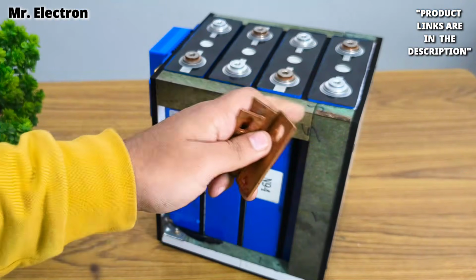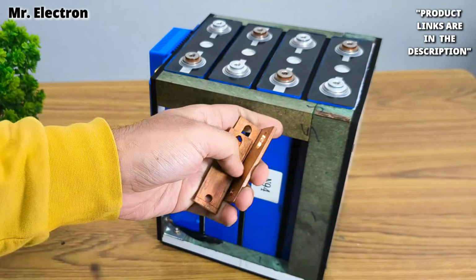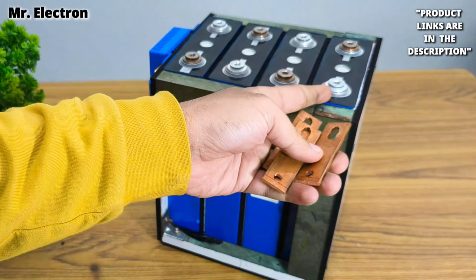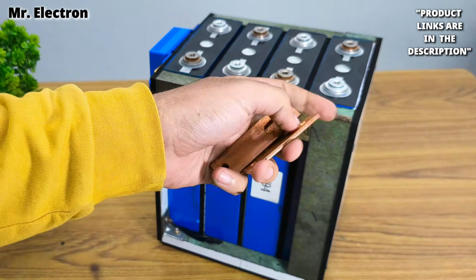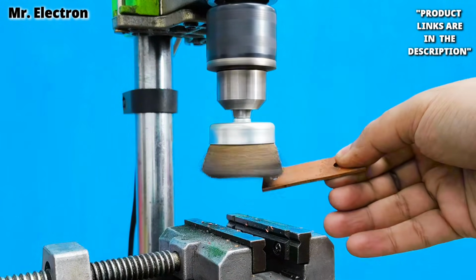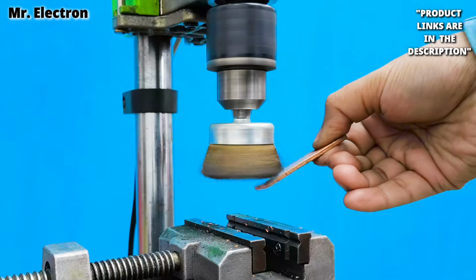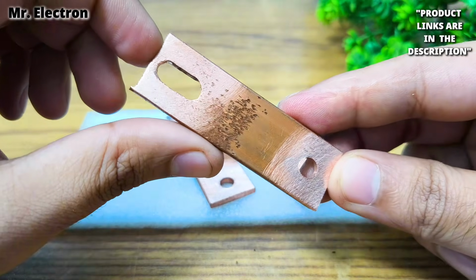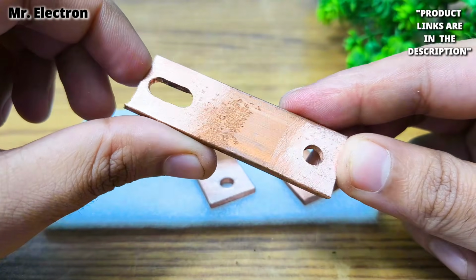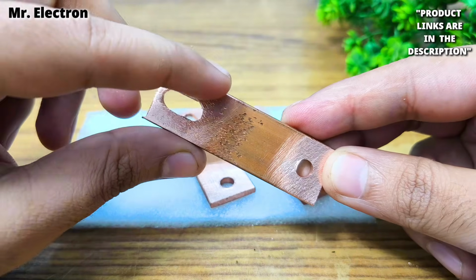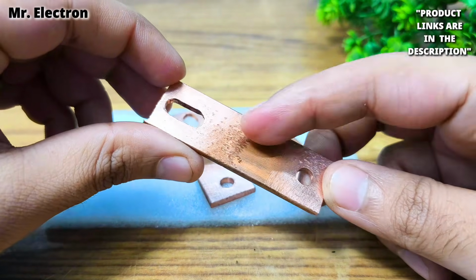Now, copper and aluminum are not friends at all. They are going to cause corrosion to each other and then finally disconnection, so I'm going to tell you the trick for this also - watch it till the end. After cleaning up the bus bars, they should look somewhat like this. You can see that I've cleaned up only the connection area. This one is like this only.